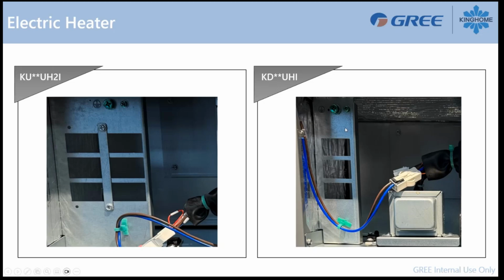On smaller tonnage, this is a picture of a 2-ton. Because a 2-ton cannot handle 15 kilowatt, they make a smaller bracket, so only one breaker can be held here. So you have only one option, which is to install a 5 or 8 kilowatt in a 2-ton system, so only one breaker is used. You see here on the picture, there's one Molex connection for the KU, and there's two here for the KD. So you have your high voltage white Molex connection, and you have the smaller one just behind it for your sensor, so your supply air sensor.